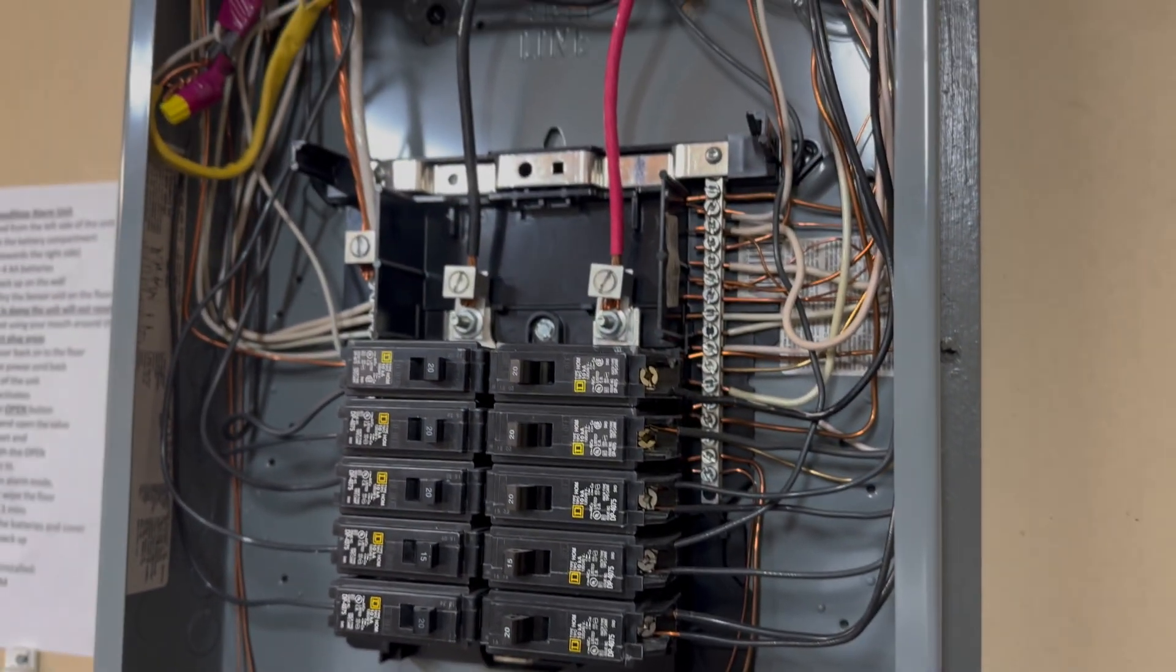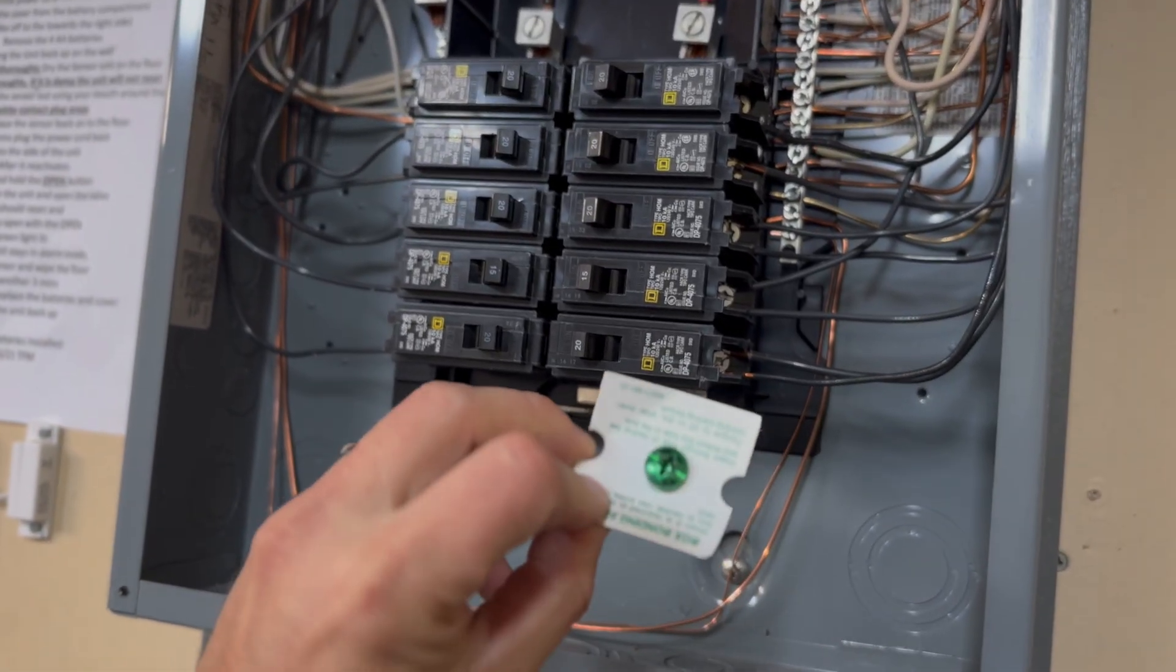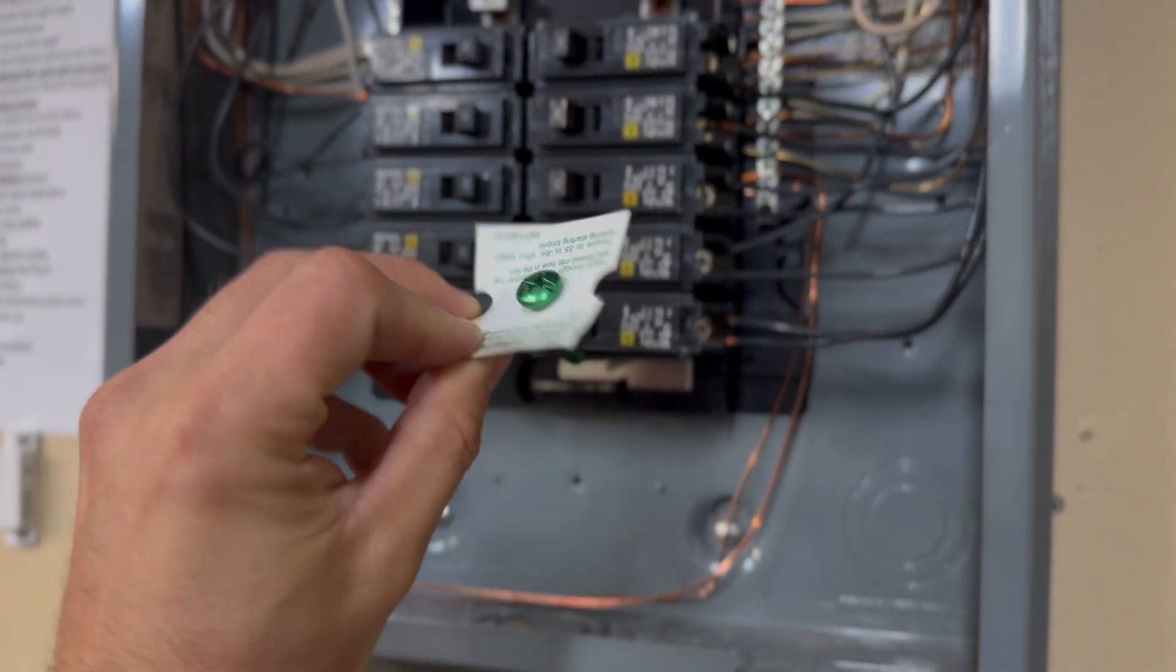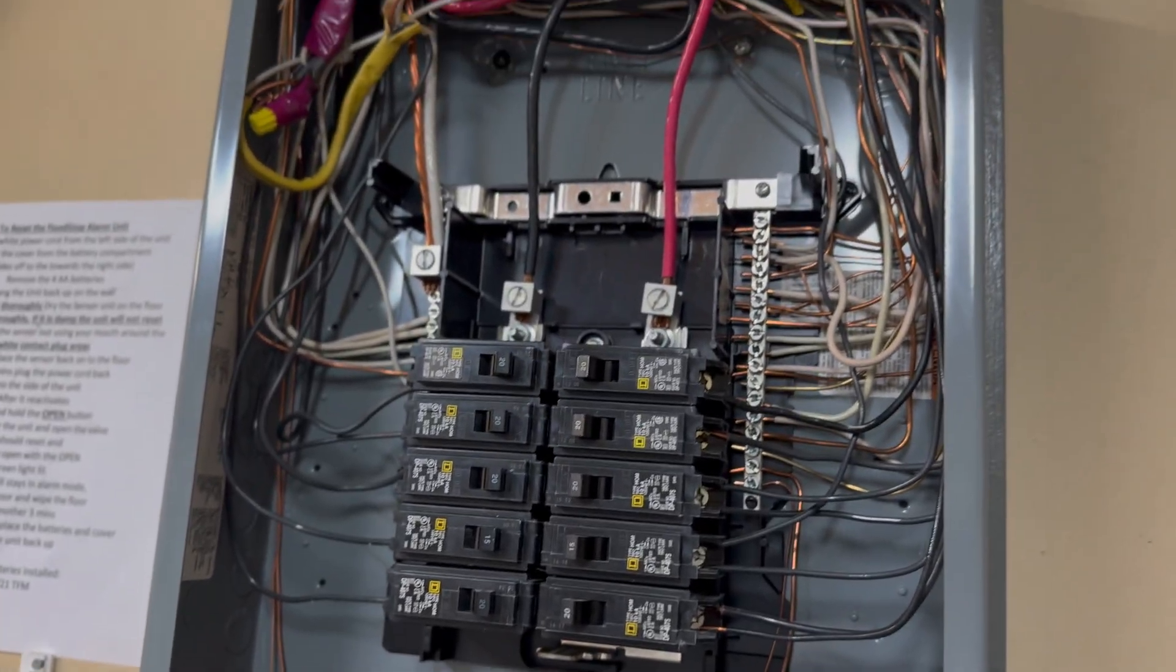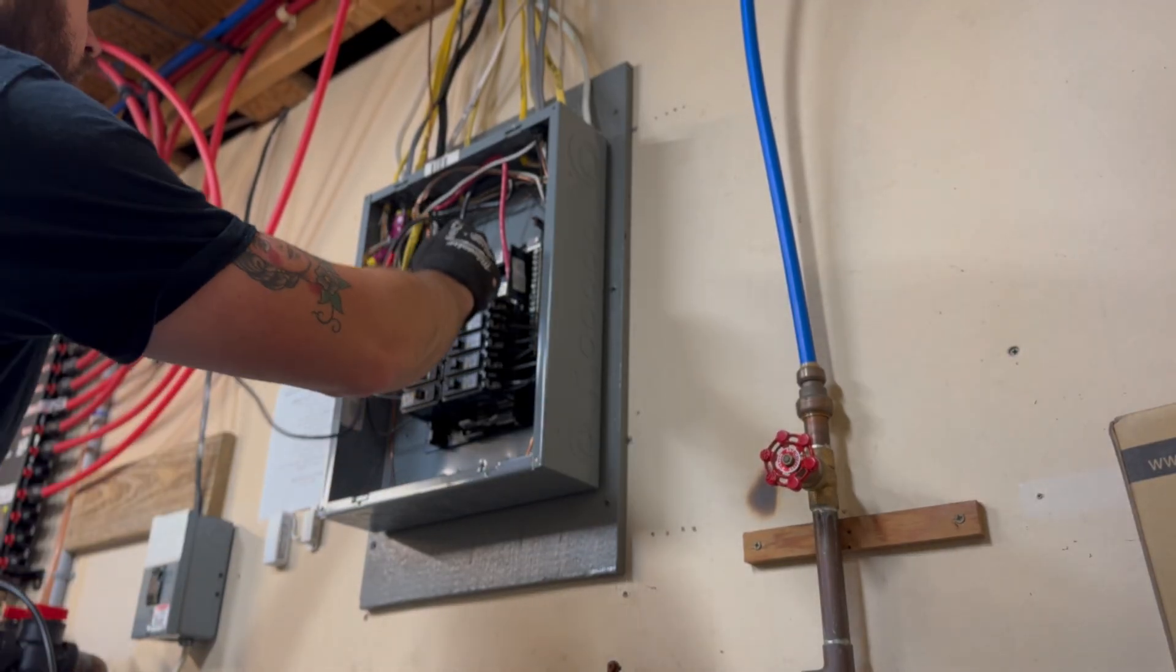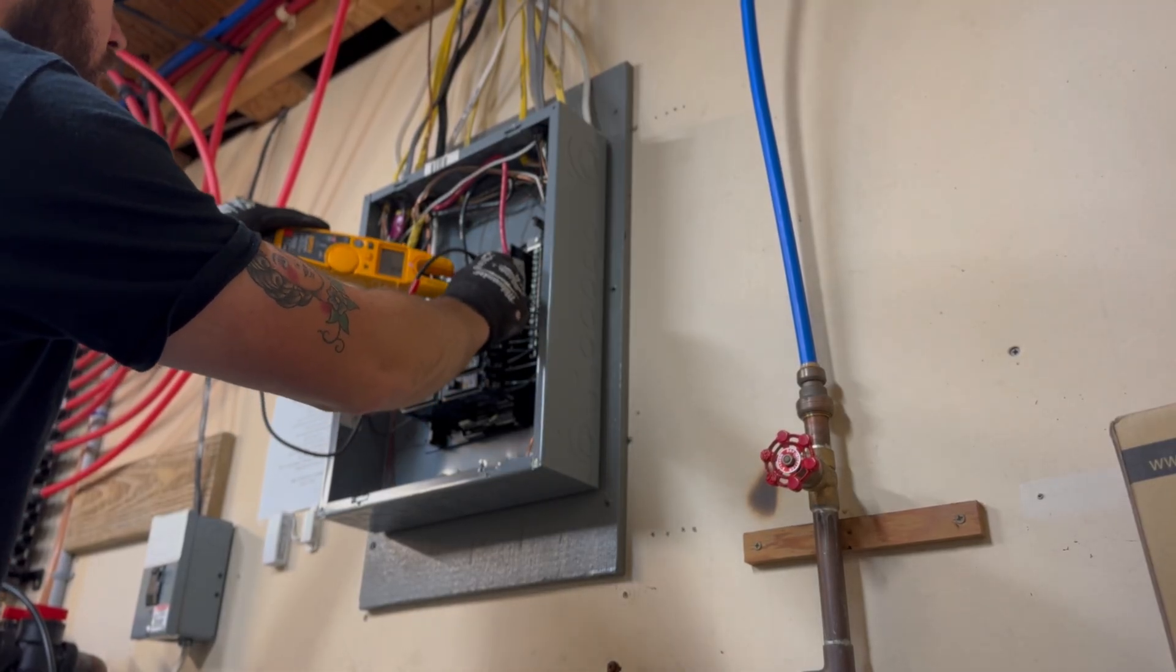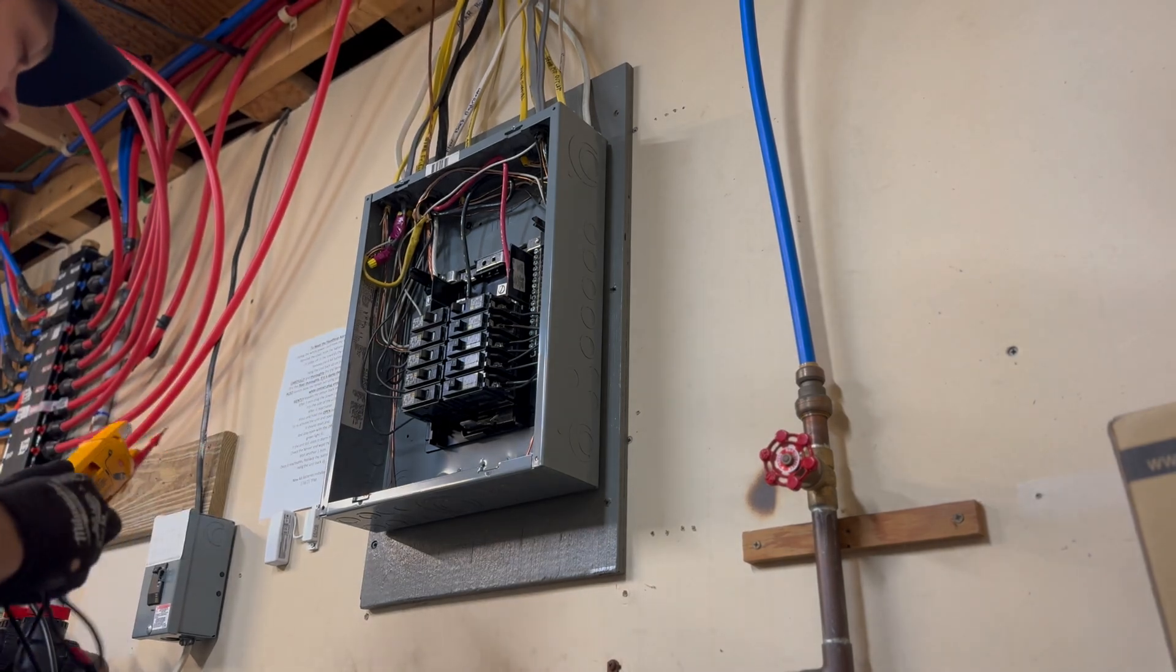The issue on top of this is that the bonding screw for this panel is just sitting inside the panel. Normally you would install this screw to bond the cabinet and the neutrals together, so the grounds and neutrals would be bonded. But they are not supposed to be bonded in this sub-panel, so that's what we're taking care of today.